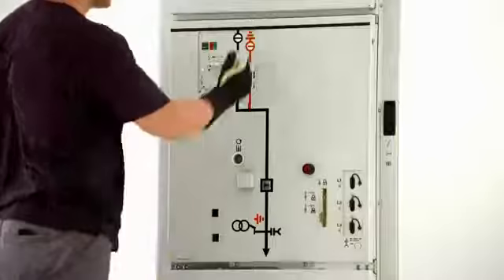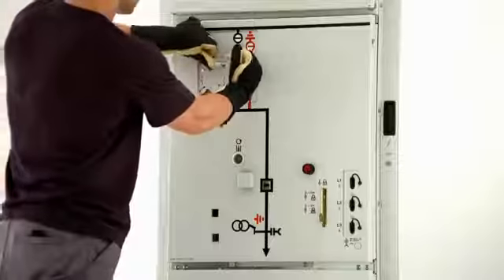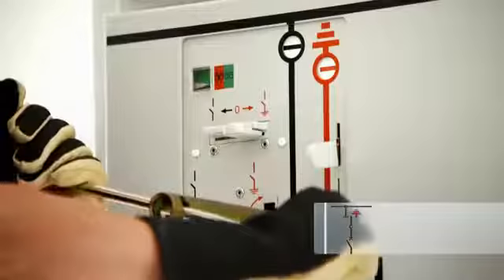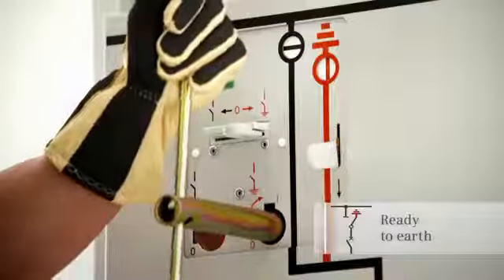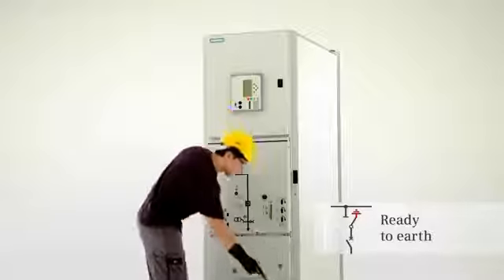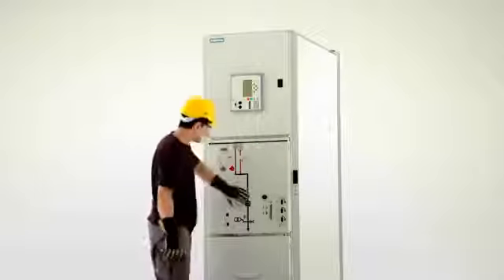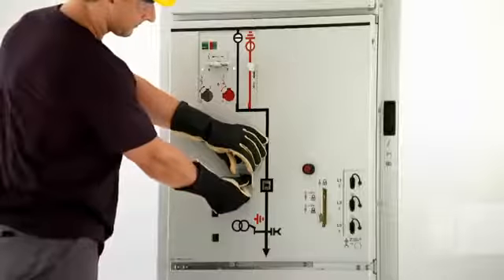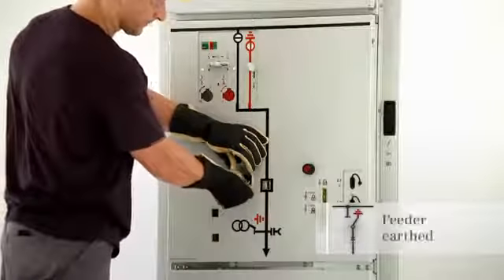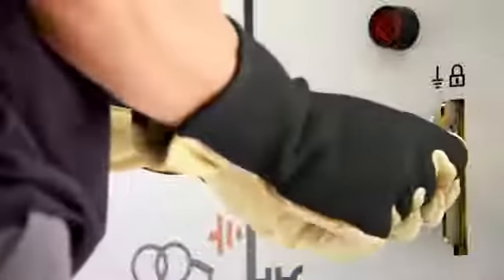The interrogation lever is now pushed down again and the control gate is pushed to the right to unlock the actuating opening for ready to earth. Turning the operating lever clockwise switches the three-position disconnector to the ready-to-earth position. The feeder is earthed by closing the circuit breaker. A locking device interlocks the switchgear in the current switch position.